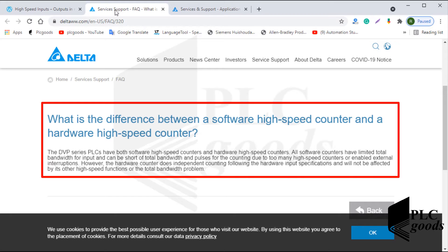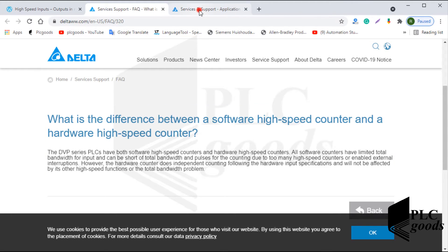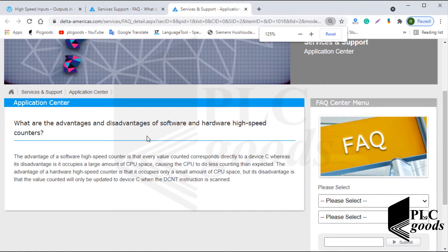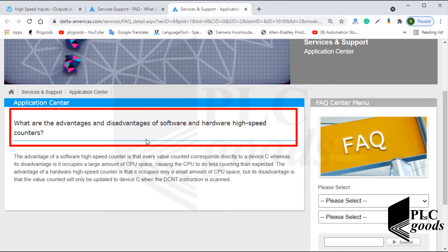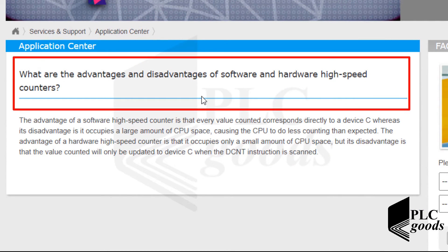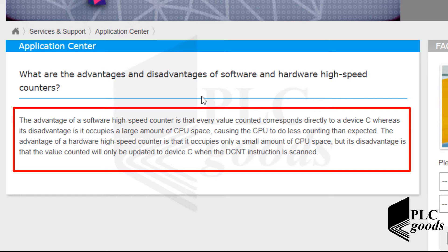Hardware high-speed counters will not be affected by other counters, interrupts, or other problems. The advantage of a software high-speed counter is that every value counted corresponds directly, whereas its disadvantage is it occupies a large amount of CPU space, causing the CPU to do less counting than expected. The advantage of a hardware high-speed counter is that it occupies only a small amount of CPU space, but its disadvantage is that the counted value will only be updated when the DCNT instruction is scanned.